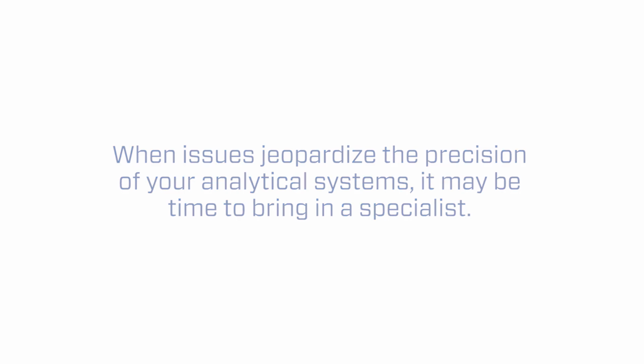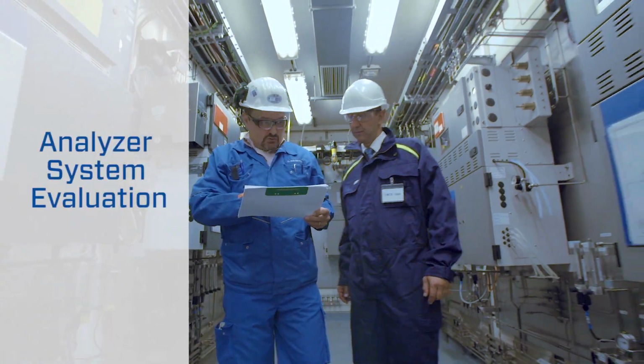So often we'll be asked to come in and look at a system after some period of time where the system's failed to live up to expectations, I would say. So, often customers will see symptoms of some underlying root cause. We often see that the initial design and the initial systems have been made according to certain PIDs. When we look into the real-time systems and at the facility themselves, they are not representative with the drawings.